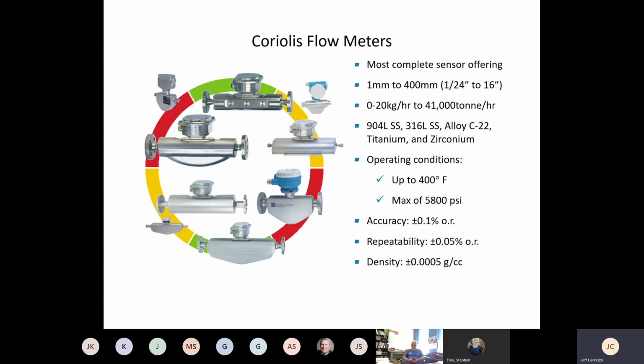But Coriolis meters have a wide rangeability. They have an extremely high accuracy and repeatability, and they are multi-output. So when we talk about Coriolis meters, keep in mind that the measurement of mass flow and density is independent. So you've got 2 variables coming out of there. Most Coriolis meters are temperature compensated, so you can also get temperature as an output. And with a straight through Coriolis meter, you can actually measure viscosity. And that's internally within the meter, without separate pressure sensors, et cetera. That's all within the meter. So they are truly a multivariable meter, and both density and mass flow are independent of one another.